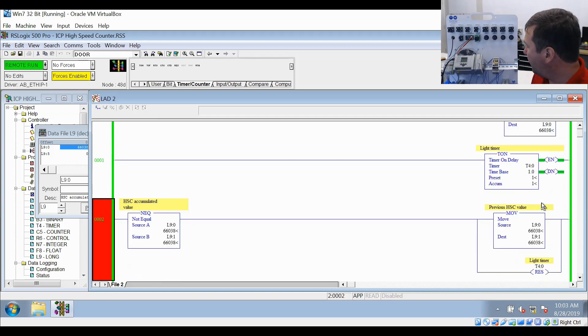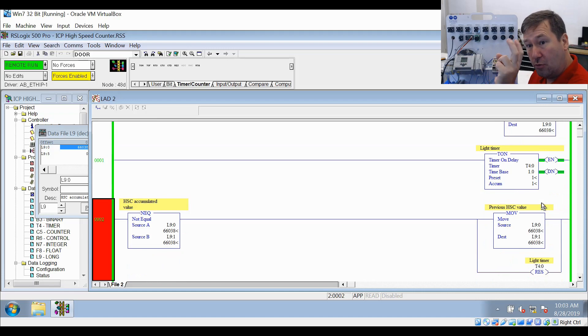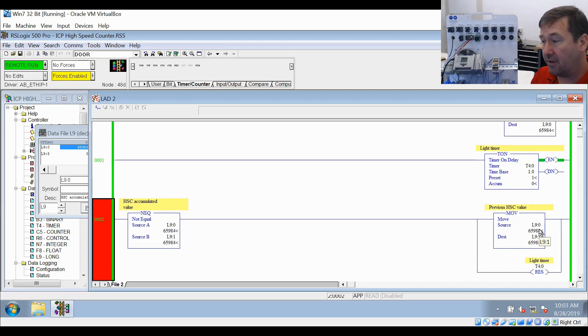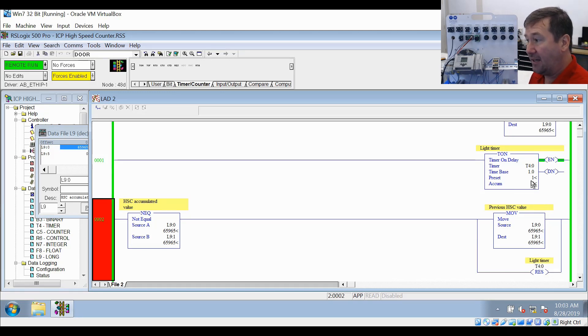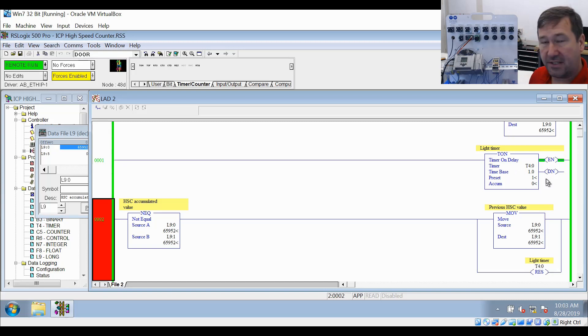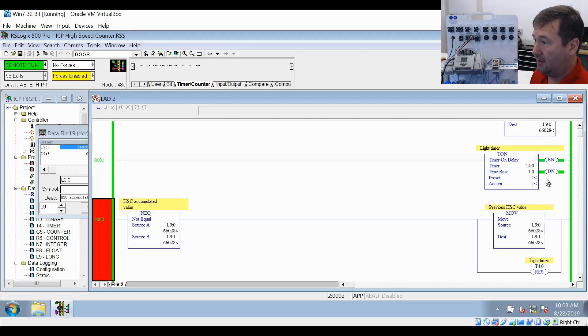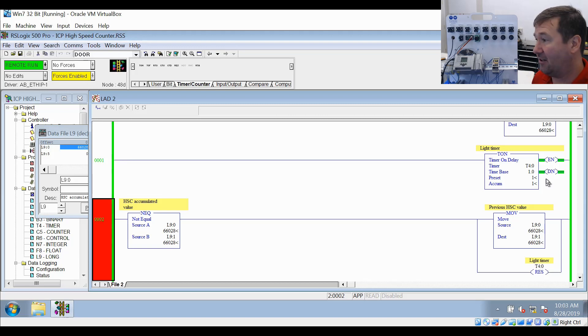Now let's go ahead and make our encoder move with our encoder simulator. We have frequency coming in - right now our encoder is going down and our timer is no longer done. We can reverse the direction; the timer is going up now and the done bit still is not set. I'm going to stop it and you can count - right at one second it is now done. So that timer done bit is telling us whether our encoder is moving or not.